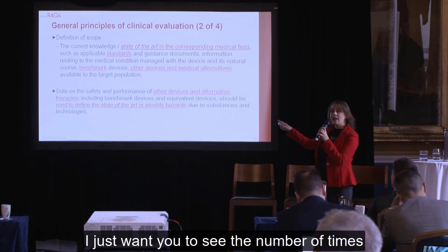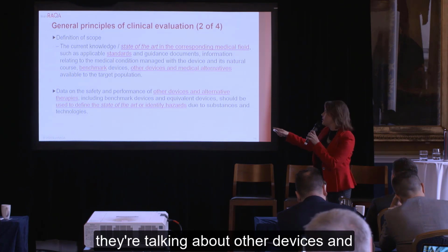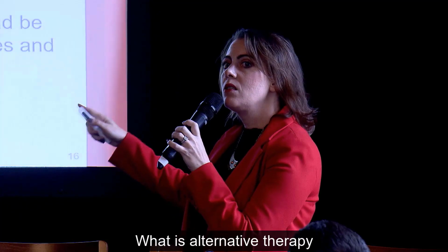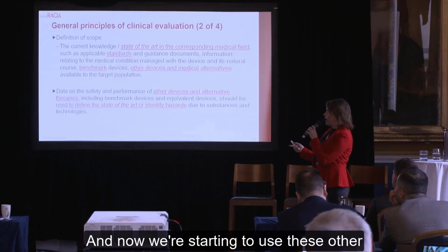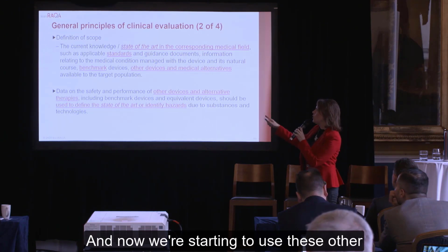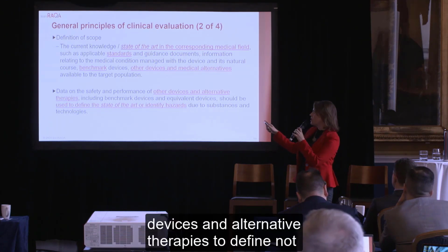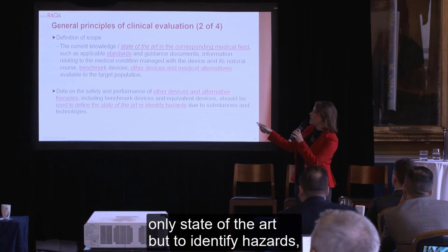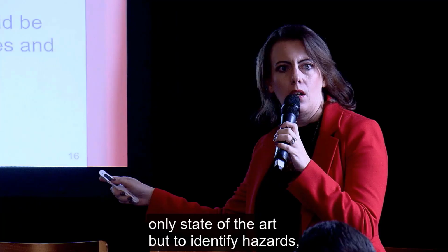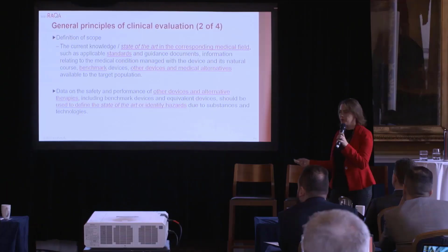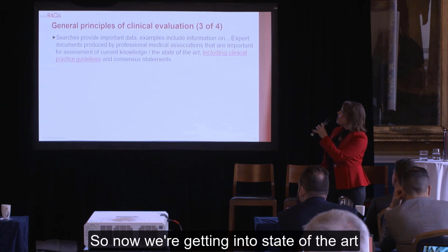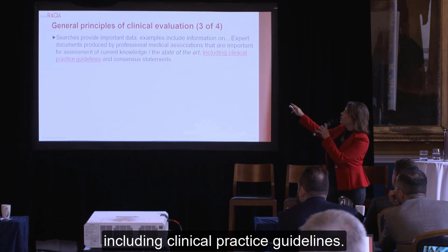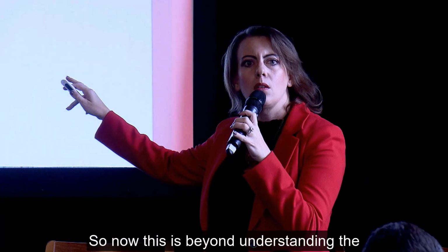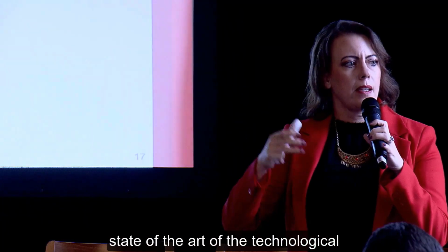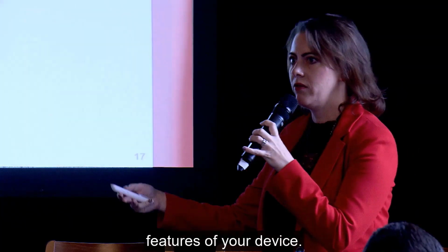Again, I just want you to see the number of times they're talking about other devices and alternative therapies. What is alternative therapy starting to sound like? Standard of care. And now we're starting to use these other devices and alternative therapies to define not only state of the art, but to identify hazards in the product's use in alternatives. So now we're getting into state of the art, including clinical practice guidelines. So now this is beyond understanding the state of the art of the technological features of your device.